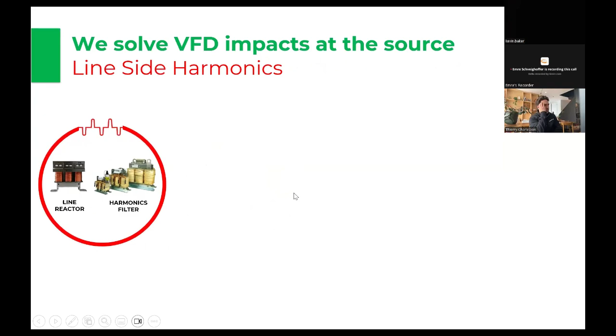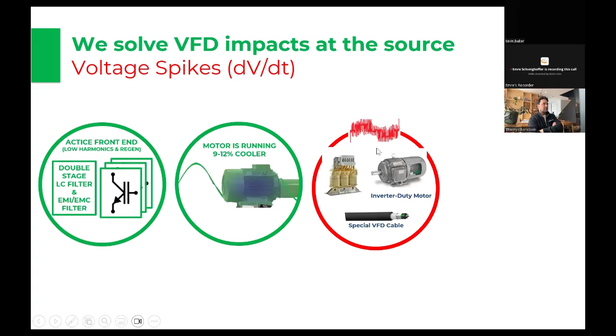in summary, we've solved these VFD impacts right at the source by changing the VFD itself. So we no longer need these bulky filters. We've replaced that with an active front end with our special patents and designs and the switches. We don't need the sine wave filters on the load side or the DV/DT filters or the reactors, and your motors end up running cooler. We don't need inverter duty motors or special VFD cables to take care of the spikes that pepper the insulation. Now you can use a standard motor. You don't need a NEMA MG1 Part 31 anymore. Now you can go with a NEMA MG1 Part 30. And you can use standard cable. You can still use shielded cable if you want, but you don't need that high-end insulation on your cables anymore.